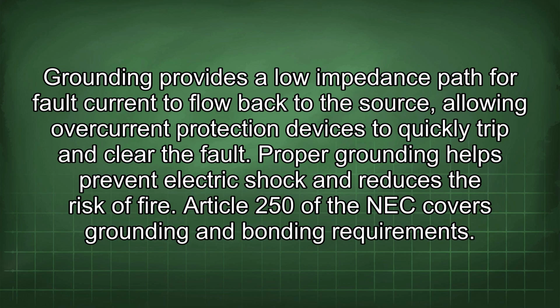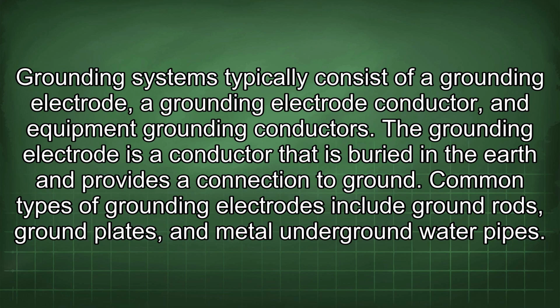Article 250 of the NEC covers grounding and bonding requirements. Grounding systems typically consist of a grounding electrode, a grounding electrode conductor, and equipment grounding conductors. The grounding electrode is a conductor that is buried in the earth and provides a connection to ground. Common types of grounding electrodes include ground rods, ground plates, and metal underground water pipes.